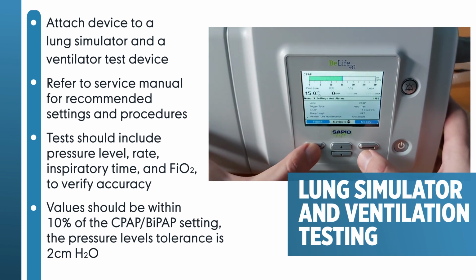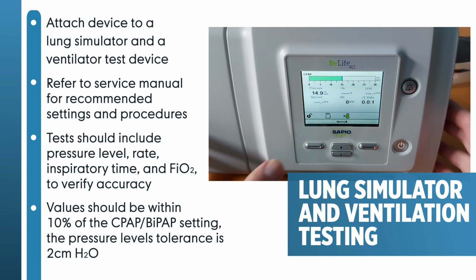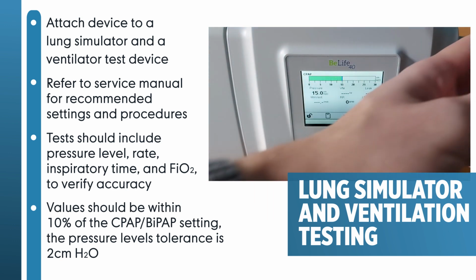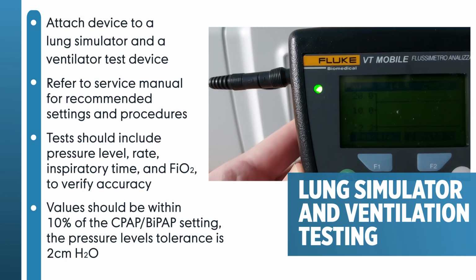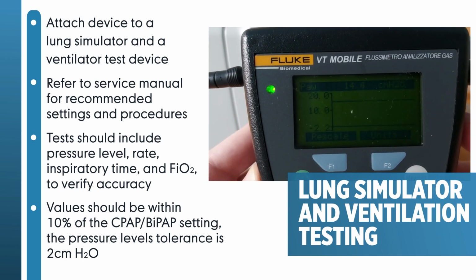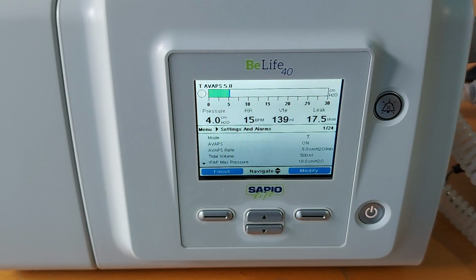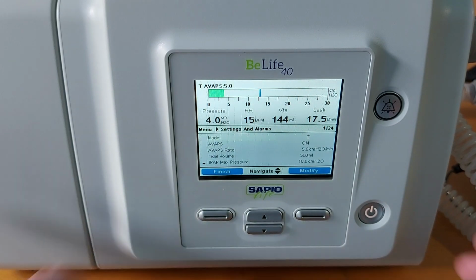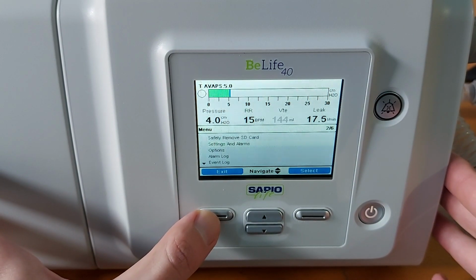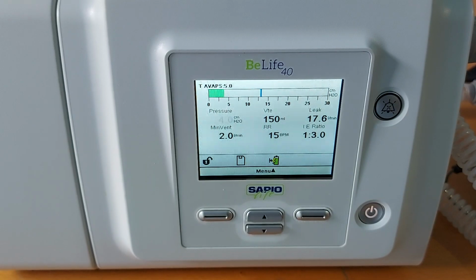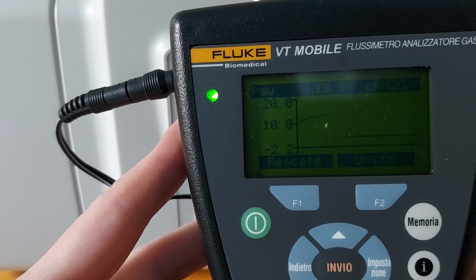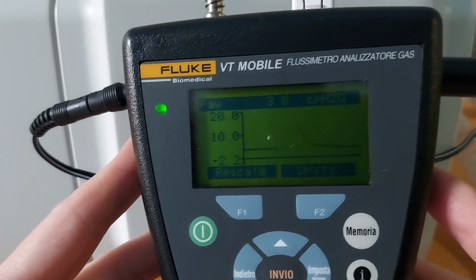Set the unit to operate in CPAP mode. Verify the unit maintains pressure level and delivers a breath to the test lung when it is triggered. Set the unit to timed mode and confirm that the device delivers breaths to the test lung at the set rate, inspiratory and expiratory time, and pressure levels.